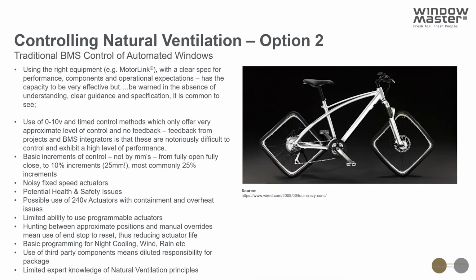There's also the possibility that BMS systems would use noisy fixed speed actuators and potential health and safety issues, or the use of mains actuators, which have to have limited operation due to overheating risks of the actuator itself. And quite often, more basic BMS systems have issues with hunting between windows. The BMS doesn't know where the vents are, and the basic programming for night cooling, wind and rain, etc., can potentially limit the performance of the systems.